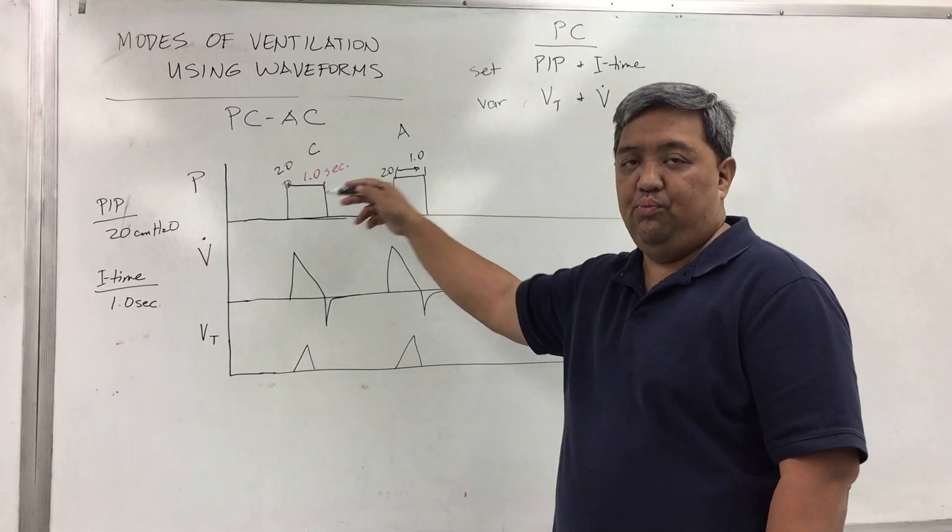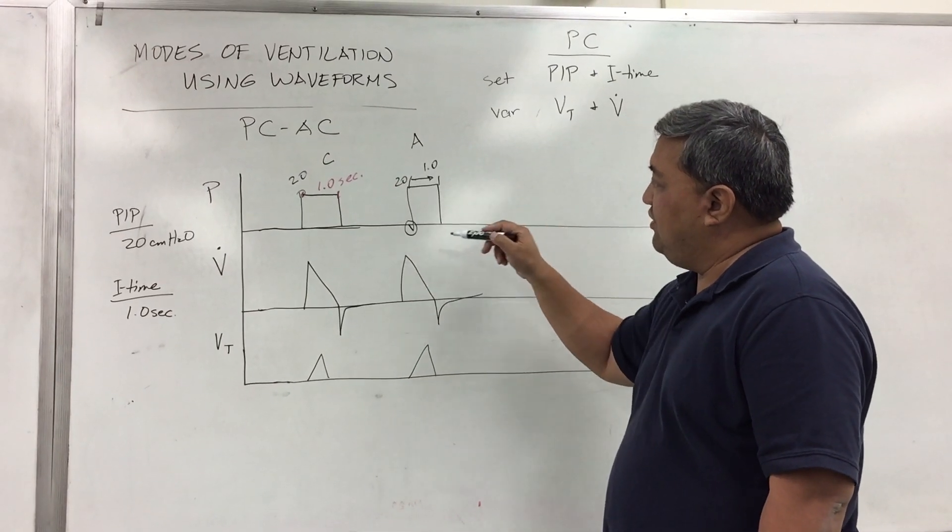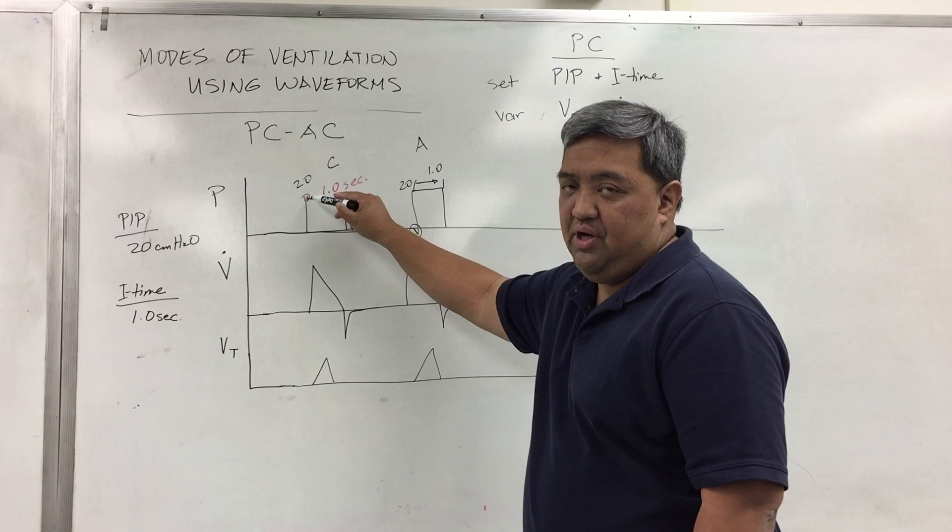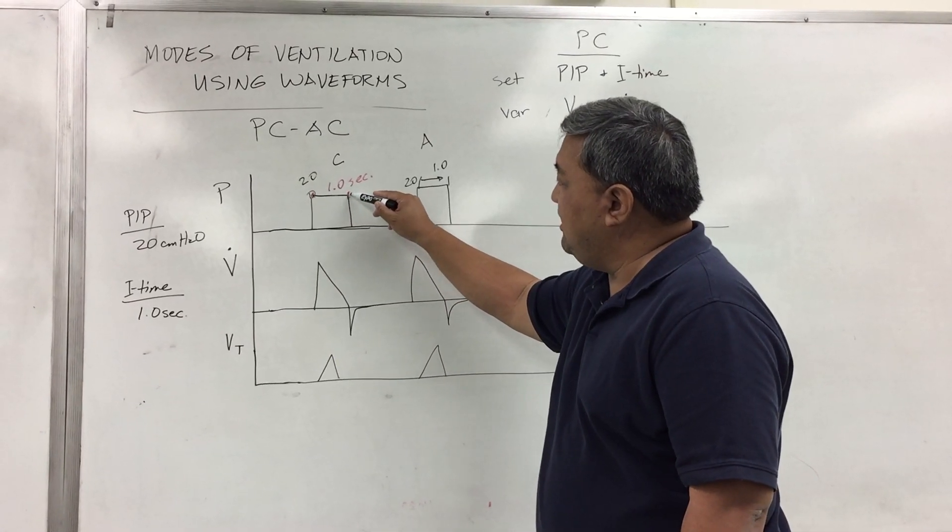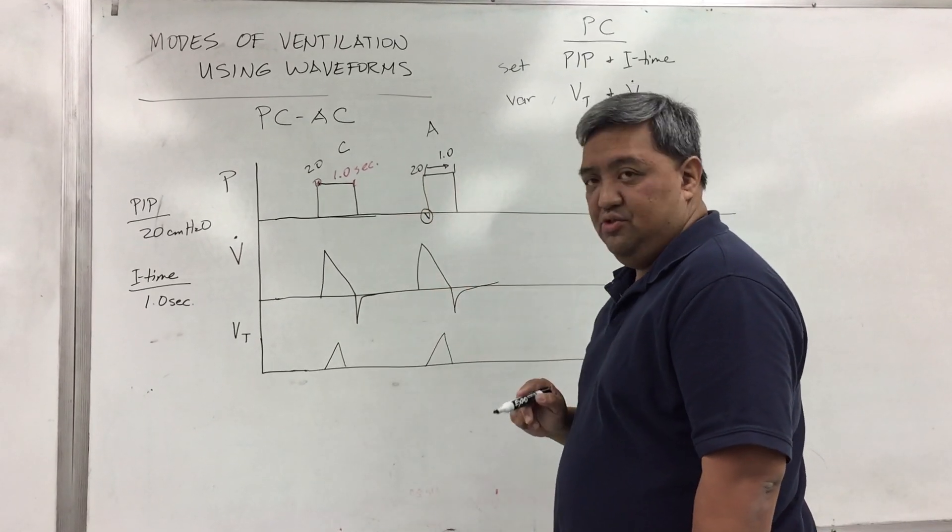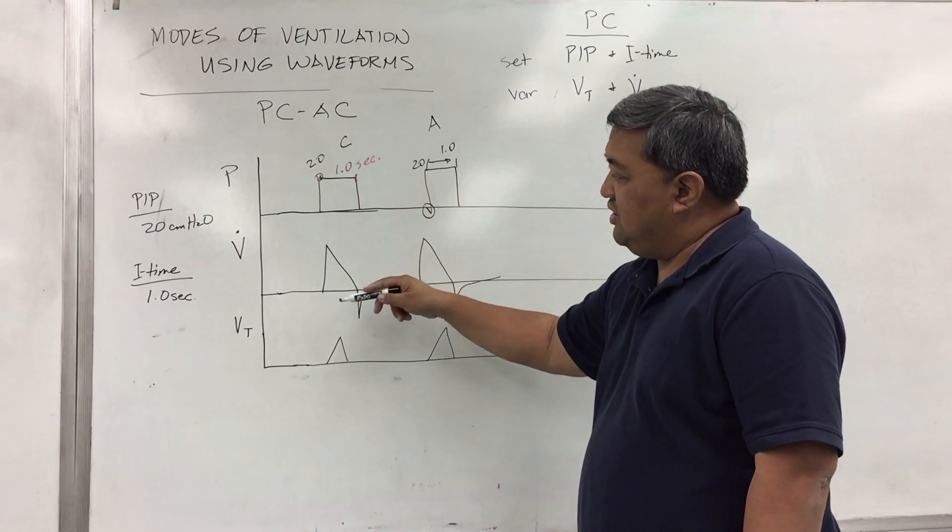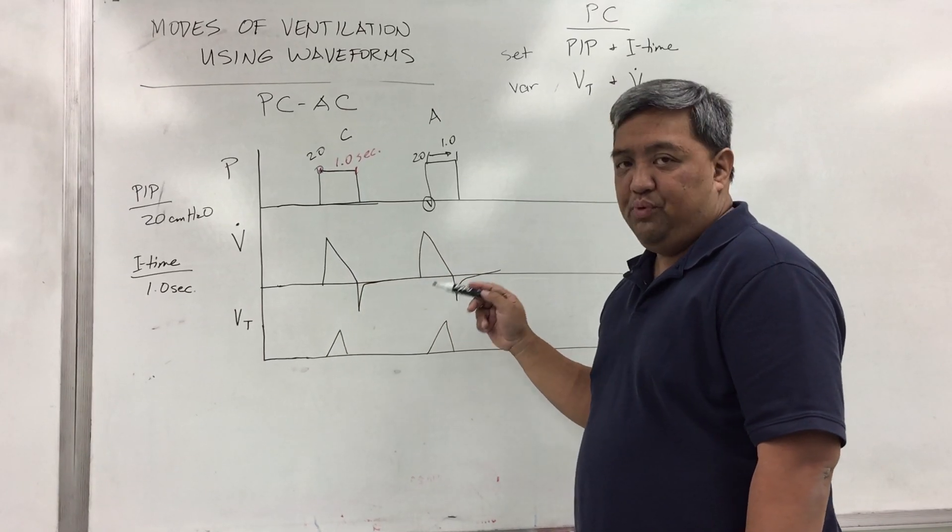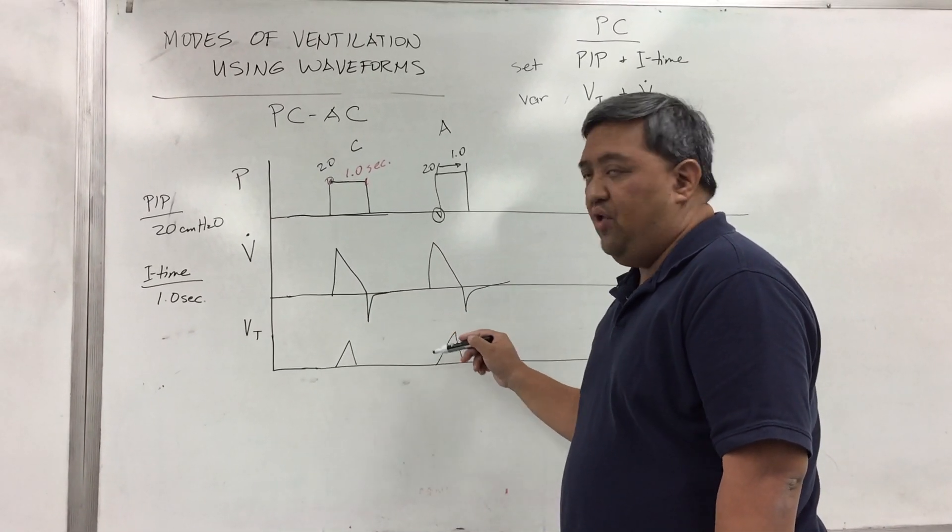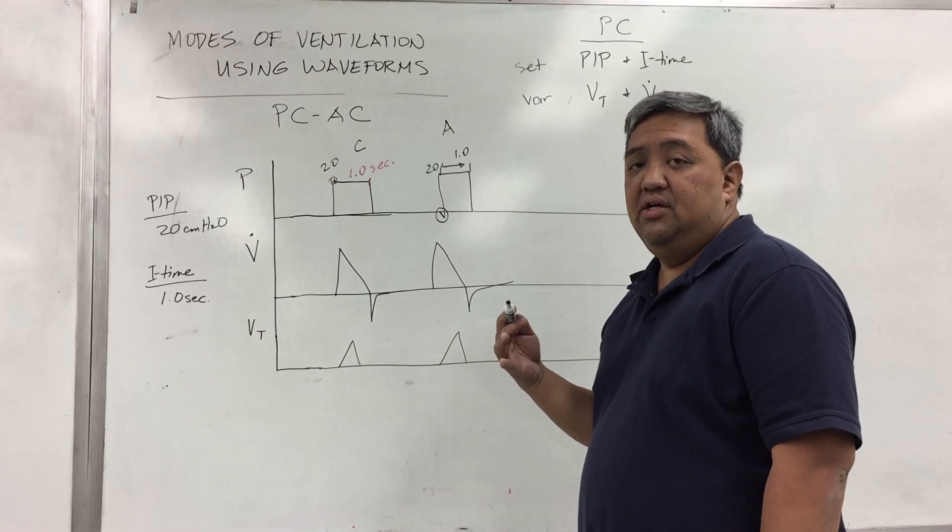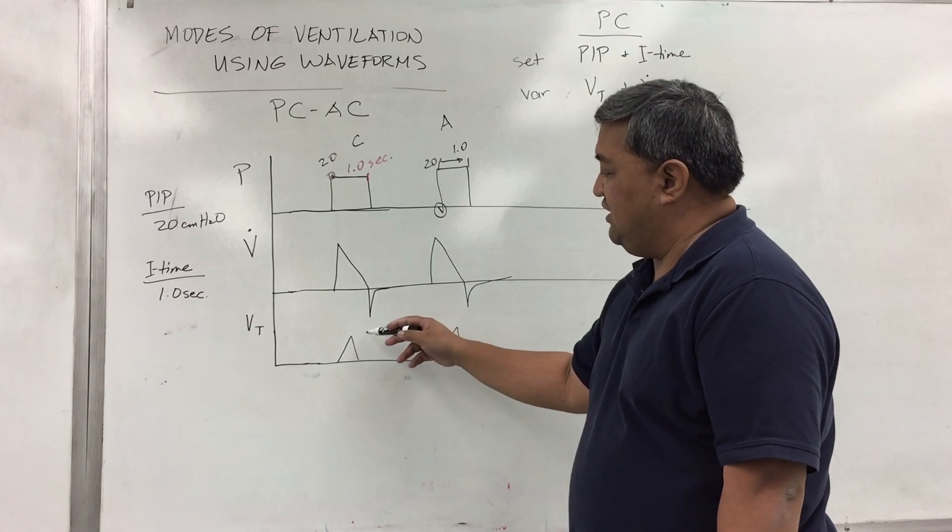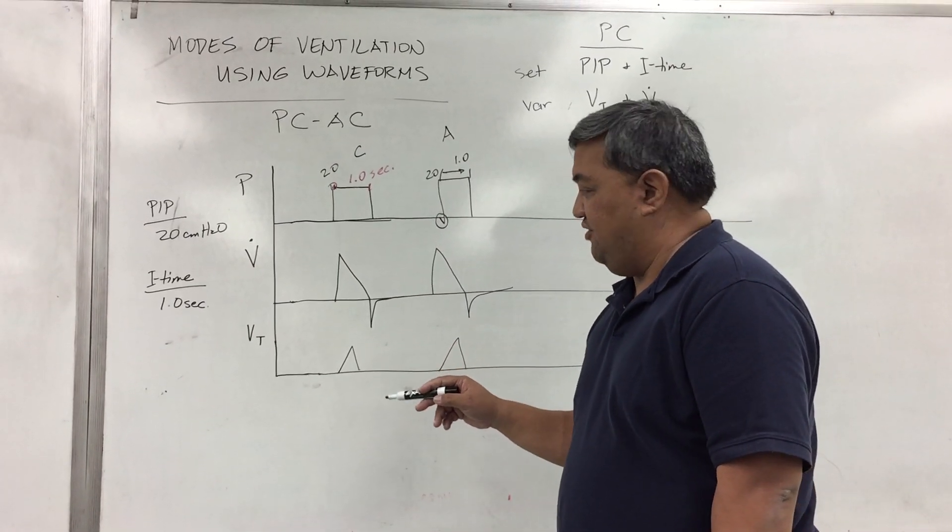This is where your peak inspiratory pressure is measured, staying consistent throughout the given time, and then it will go into exhalation. The flow waveform on pressure control is always descending or a ramp. The volume will vary depending on the patient's inspiratory effort, as well as the resistance and compliance of the patient.